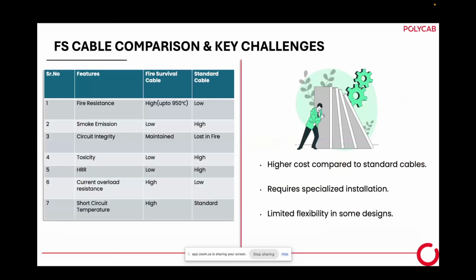Now, it is a small comparison of fire survival cable compared to standard cable. Fire resistance is very high; standard cable, it is low. Smoke is low; standard cable, it is high. Circuit integrity is maintained; standard cable is lost in fire. Toxicity is very, very low; standard cable, it is high. HRR, as I told you, heat release rate is very low, but standard cable, it is high. Current overload and short circuit temperature is high. It is a little bit of a challenge.